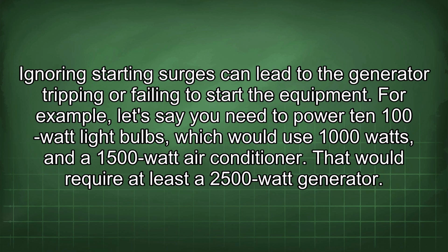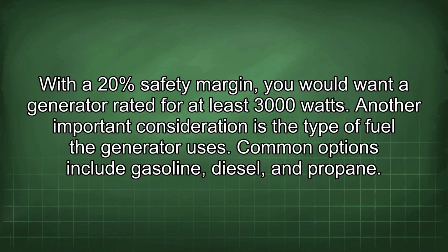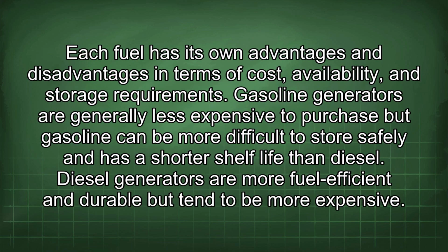For example, let's say you need to power 10 100-watt light bulbs, which would use 1000 watts, and a 1500-watt air conditioner. That would require at least a 2500-watt generator. With a 20% safety margin, you would want a generator rated for at least 3000 watts. Another important consideration is the type of fuel the generator uses. Common options include gasoline, diesel, and propane. Each fuel has its own advantages and disadvantages in terms of cost, availability, and storage requirements.